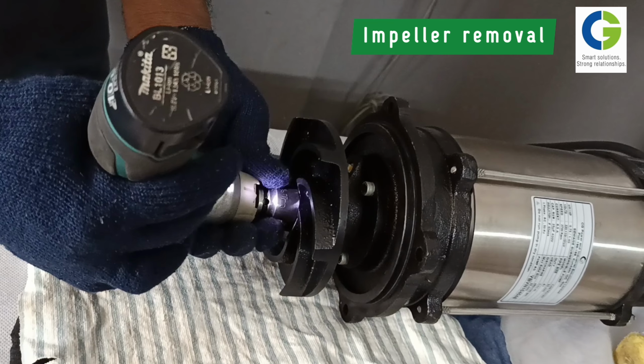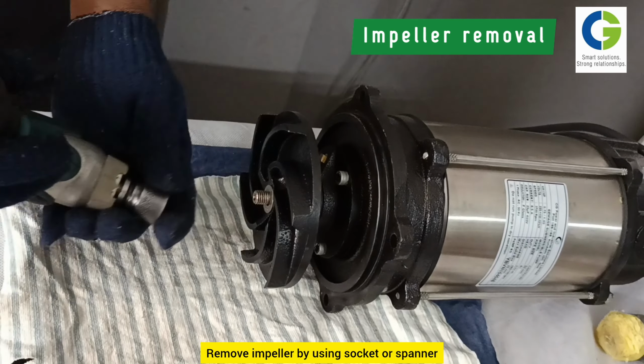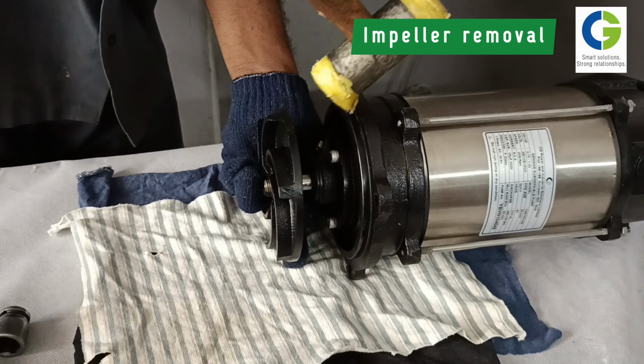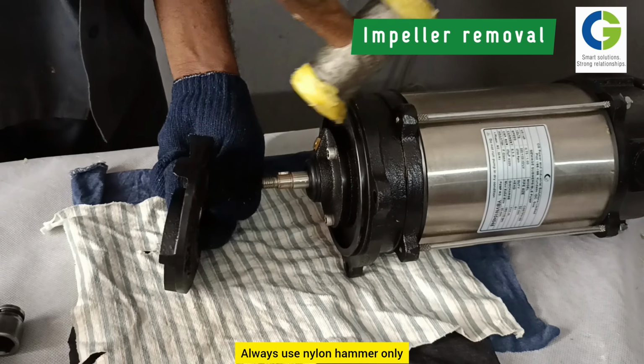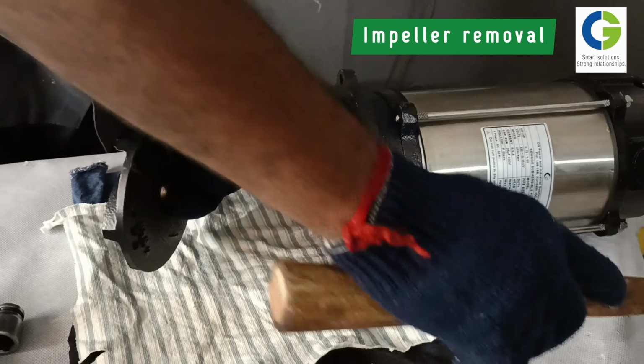Inspect the impeller. If worn out, replace it. Remove the impeller by using a socket or spanner. Always use a nylon hammer only. Now we'll see how we can replace the oil seal or mechanical seal. This is the sand slinger bush. Remove the drain plug and Allen bolt. In this oil chamber, replace the old transformer oil with new transformer oil. This is the oil chamber.